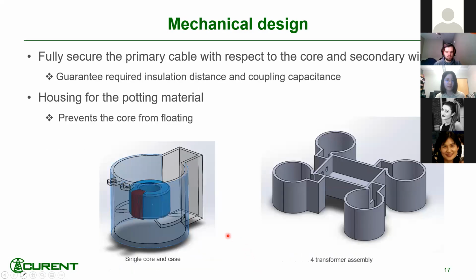And another part is the mechanical design, because we have to securely fasten the primary cable with respect to the core and the secondary windings in place, so that the coupling capacitances would be as designed. And also, this transformer needs a housing for the potting material. Because I have 4 cores in the topology, this is the assembly case that I have designed.